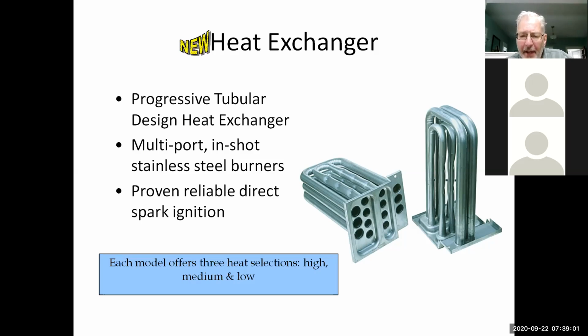It's an in-shot negative pressure heat exchanger. The inducer draws the flue gases through it. And we've got 3 different heat exchangers, a low, medium, and high heat exchanger, and they're not interchangeable. Typically in the northern climates, we stock the high heat units. If you're looking for a low heat unit, you can't just change the gas pressure or change the orifices or the heat exchanger, because they physically are different units.